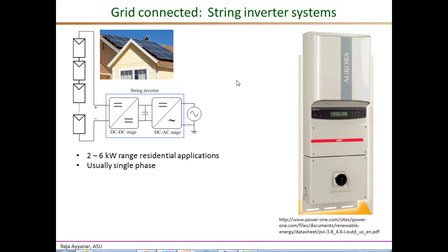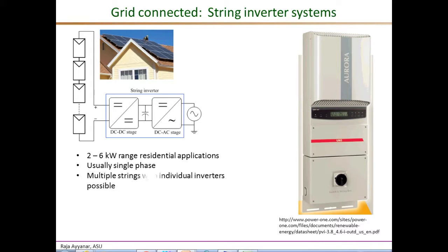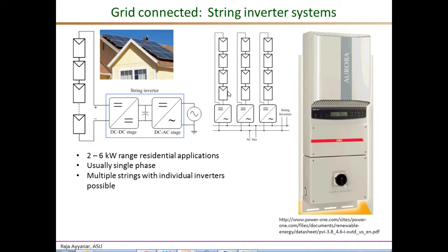The next type is the string inverter system, usually used in residential applications with power ratings ranging from 2 kilowatts to about 6 kilowatts, and they tend to be single-phase systems. In this configuration, series-connected PV panels produce a DC voltage roughly in the range of 300 to 500 volts DC, which is converted to grid-quality AC through the string inverter. It is also possible at higher power levels to have multiple PV strings, each connected to an individual inverter, producing about 400 to 500 volts DC converted to AC independently.